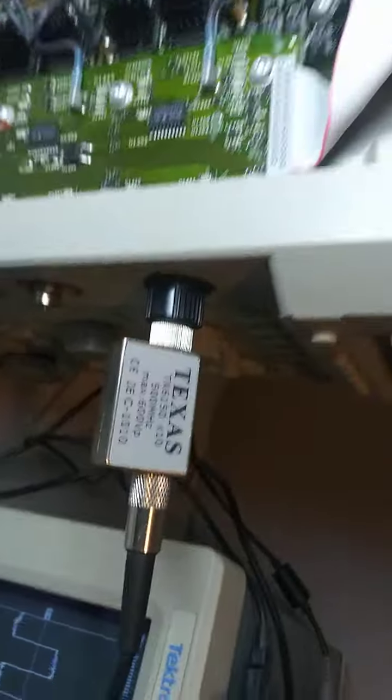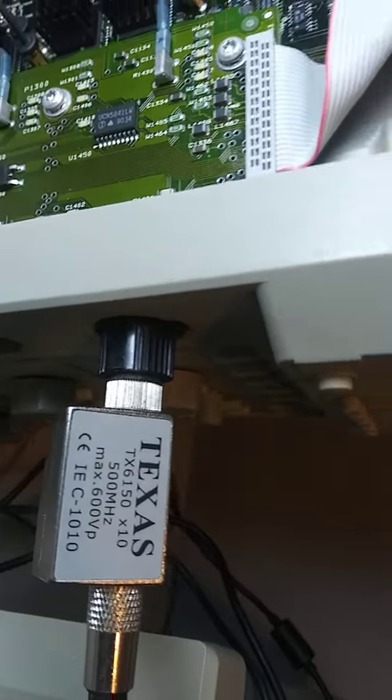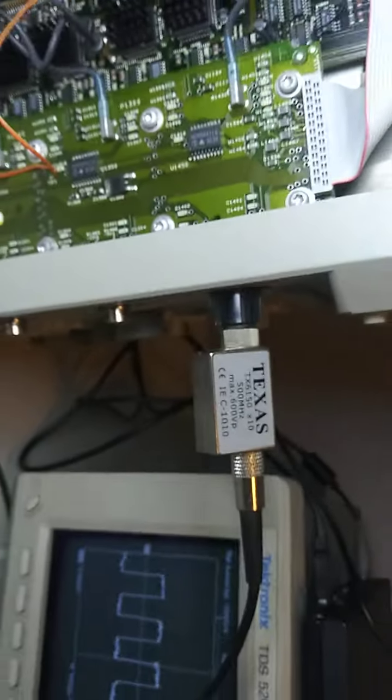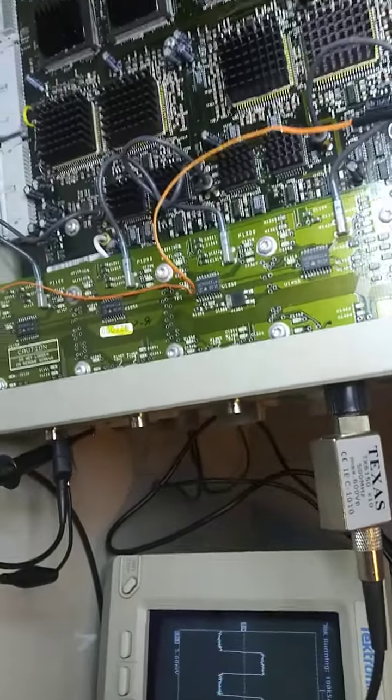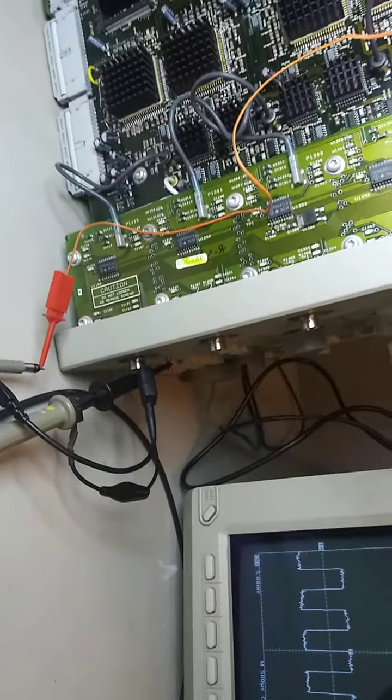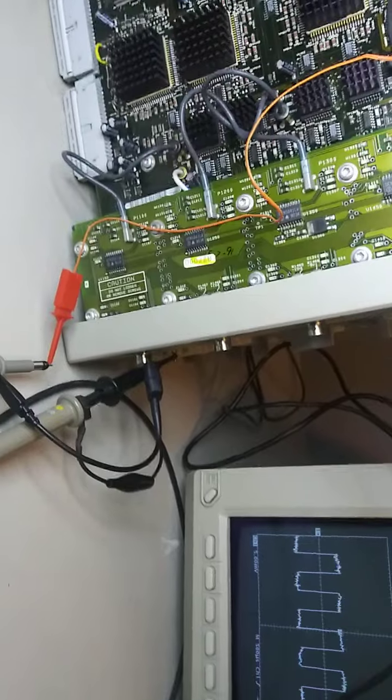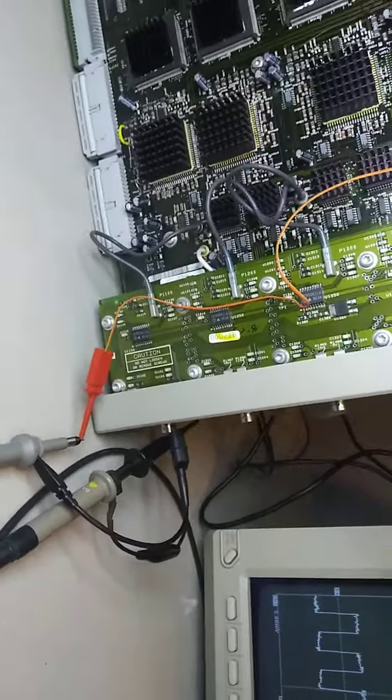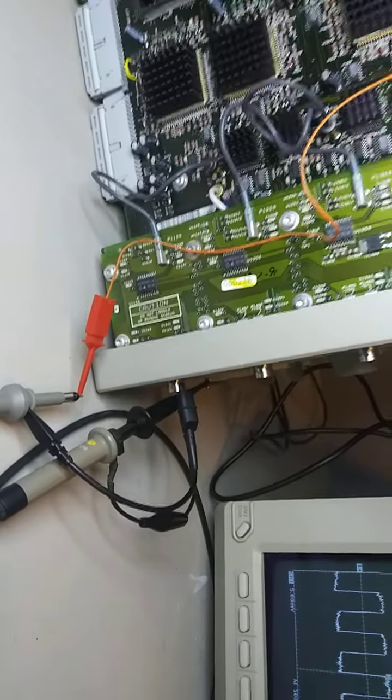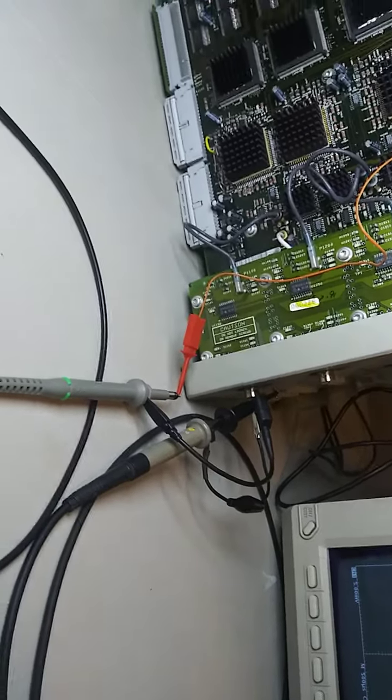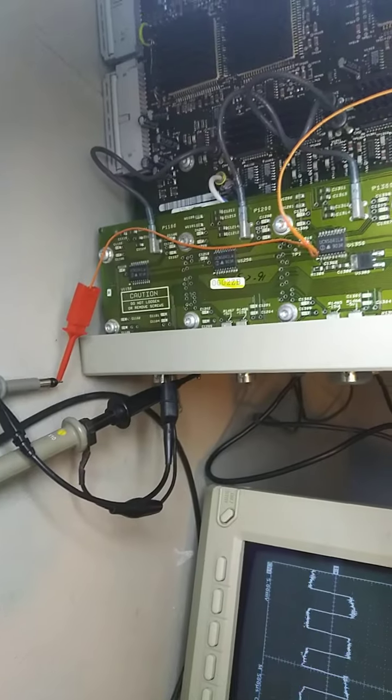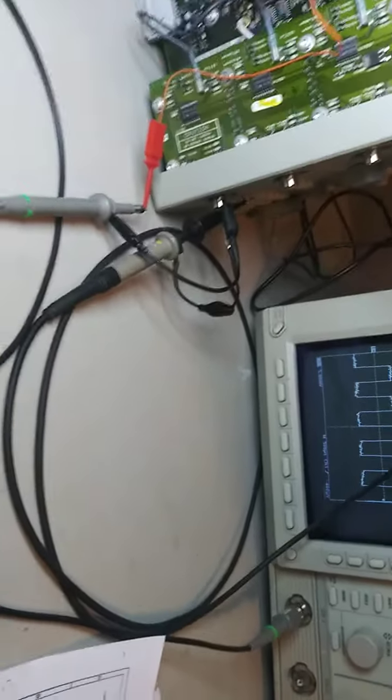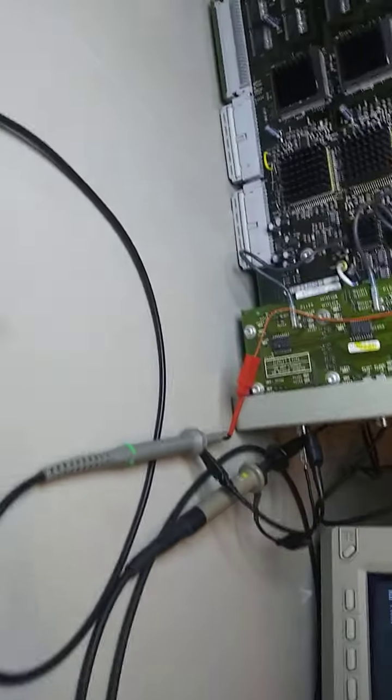Now as I turn the vertical offset clockwise, it'll be applying a more negative voltage to the inverting input, which is pin 21 of the preamp, which should cause it to go down. But remember, pin 2 which goes to the trigger is inverted itself, so it should go up. Now let's see what it does on channel 1.